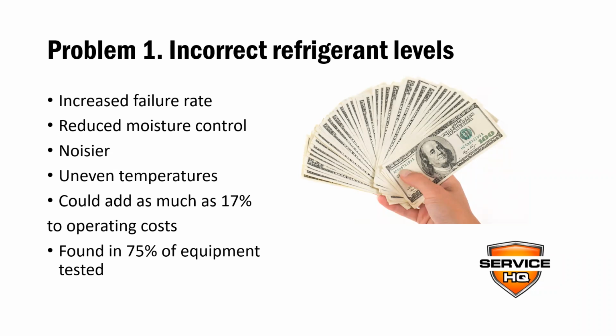The unit can actually operate noisier than normal. It can create those uneven temperatures that we talked about. It could add as much as 17% to the operating cost. And this literally is found in 75% of equipment tested. Most units are not charged properly. So, with all of that taken into consideration, you don't want to be paying all this extra money to the utility company because of an incorrect refrigerant level.